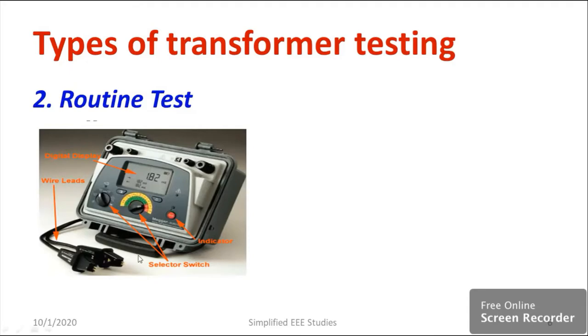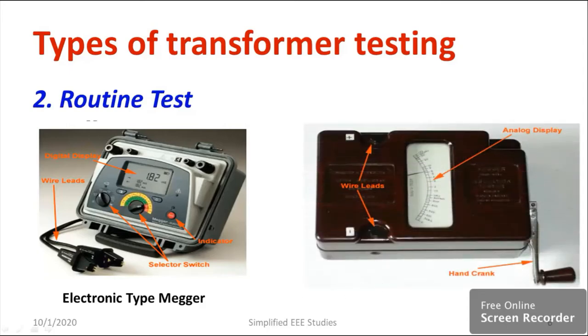As you can see, this is the electronic type, battery-powered Megger. We will be directly inserting the leads into the transformer winding and getting the reading in terms of mega ohms. This type of Megger is now commonly used. The hand-operated type Megger has an operating handle driving a generator, with connecting leads inserted in the winding section. It gives a direct analog display, while the electronic type provides a digital display.